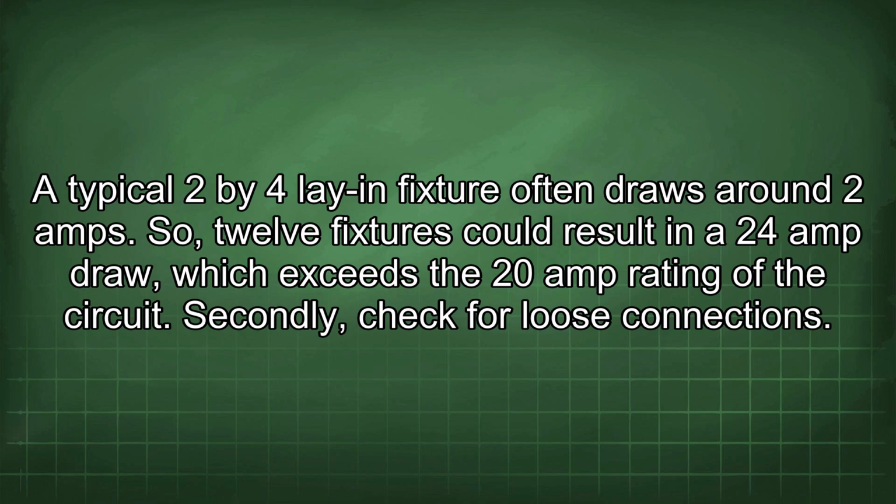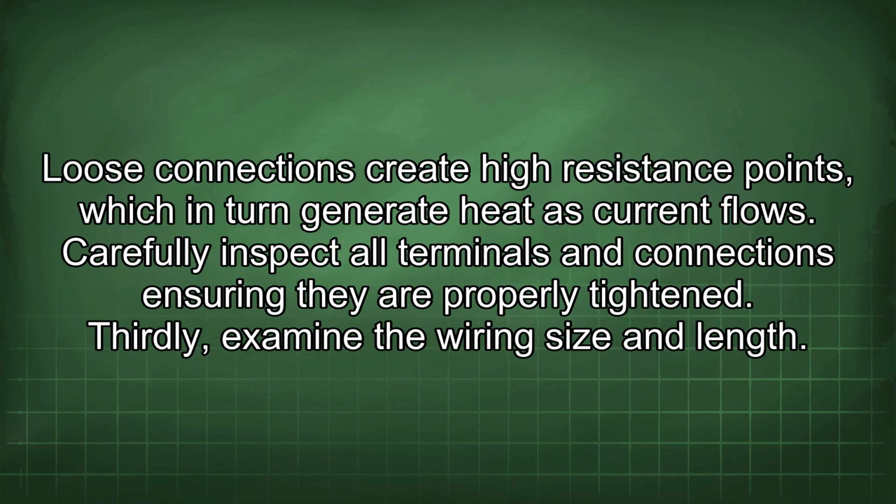Secondly, check for loose connections. Loose connections create high resistance points, which in turn generate heat as current flows. Carefully inspect all terminals and connections, ensuring they are properly tightened.